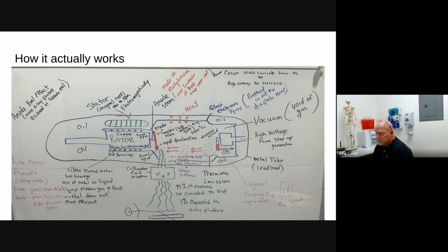The characteristic radiation depends on the type of metal, whether it be molybdenum, rhodium, or tungsten, primarily tungsten. And like I said before, most of the X-rays that are emitted are Bremsstrahlung X-ray photons. So rapid deceleration hits the tungsten plate at the focal spot, an interaction takes place, and X-rays are formed, whether they be Bremsstrahlung or characteristic.